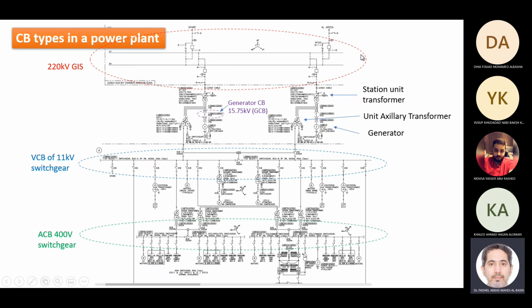So what's a switchgear? It is the combination of all of this: buses, breakers, CTs, VTs for measurements and protection, earth switches, and disconnectors. All of this is called a switchgear. Our focus today is not the switchgear, we focus on the breaker types only. So this is 220 kV gas insulated switchgear, and there are different types of switchgear based on the insulation medium. Here this bus bar is split into two sections, so this is a bus tie.